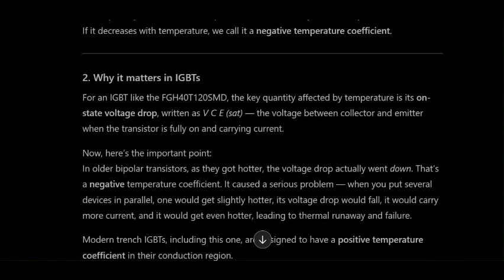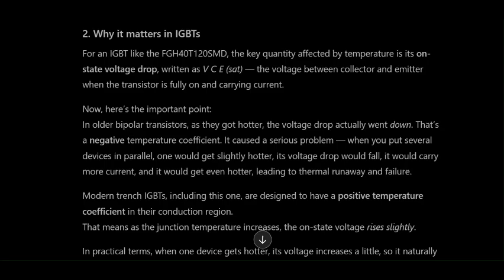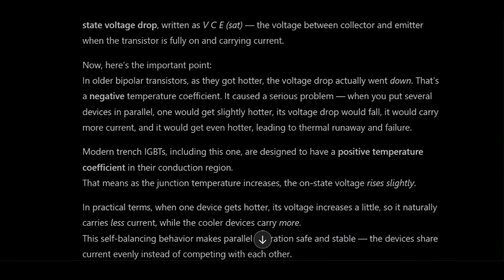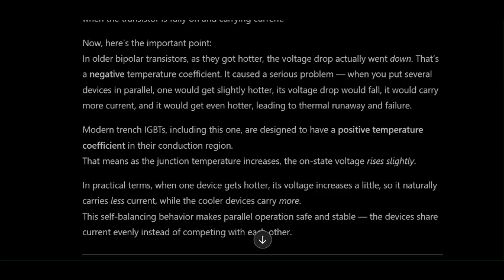Why it matters in IGBTs: for an IGBT like the FGH40T120SMD, the key quantity affected by temperature is its on-state voltage drop, written as VCE sat, the voltage between collector and emitter when the transistor is fully on and carrying current. Now, here's the important point. In older bipolar transistors, as they got hotter, the voltage drop actually went down. That's a negative temperature coefficient. It caused a serious problem. When you put several devices in parallel, one would get slightly hotter, its voltage drop would fall, it would carry more current, and it would get even hotter, leading to thermal runaway and failure.